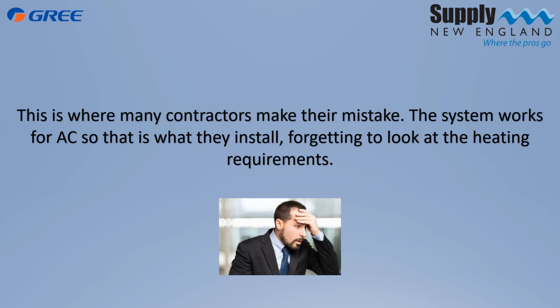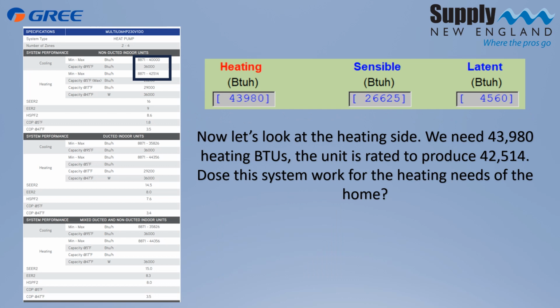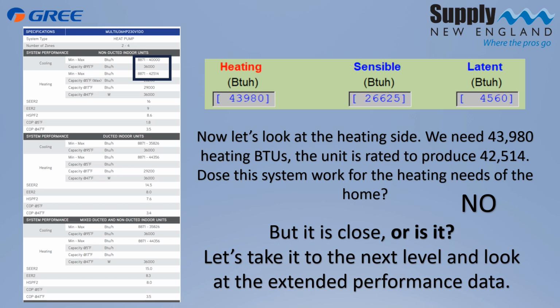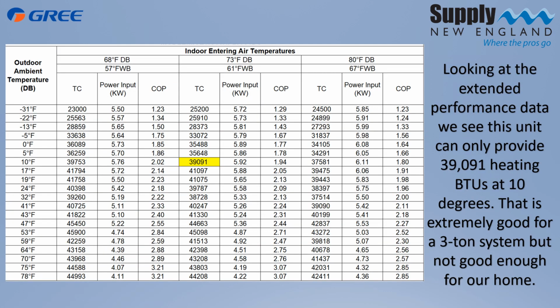Forgetting to check the extended data on the heating side. So let's take a look at that. In this case, it's pretty easy to see that it's just not going to cover our load. The maximum capacity of this system is 42,514. We need 43,980. So does it work for our heating needs? No, it doesn't work. But it's close. Or is it? I'm guessing you know by now that I wouldn't ask that question if it did. So let's take a look at why.